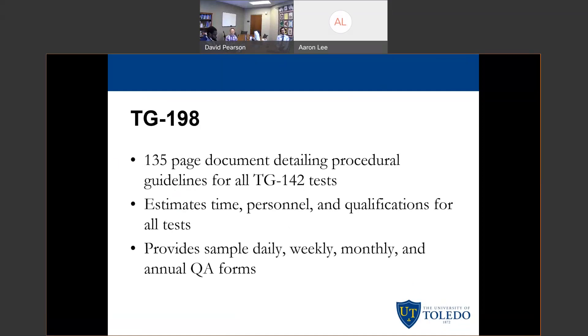What TG-198 does is it estimates the time, personnel, and qualifications for all tests, and then provides sample daily, weekly, monthly, and annual QA forms. It also tells you how you should be able to perform each test, what kind of equipment you would need, things to avoid, tolerances, and things like that.